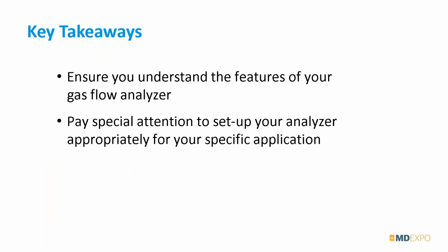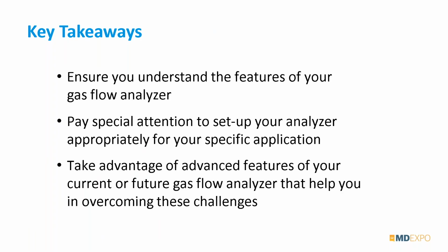If there's just one thing I want you to remember, it is the gas standard. Make sure that the gas standard matches the gas standard used by the device under test, because this can really lead to a lot of reading errors. And that's also the thing that we see most out there in the field, because as I mentioned, the trigger settings typically work with the default settings, but the gas standard is really something that you need to make sure is correct. And then take advantage of these advanced features.